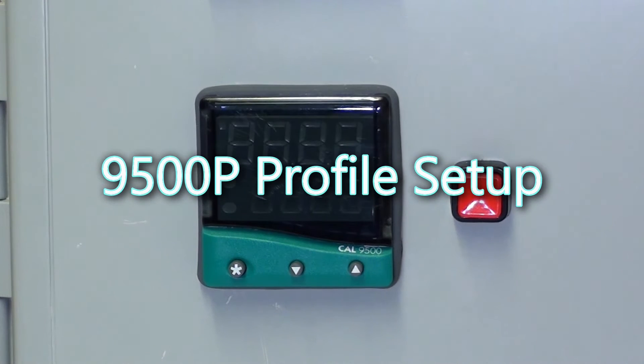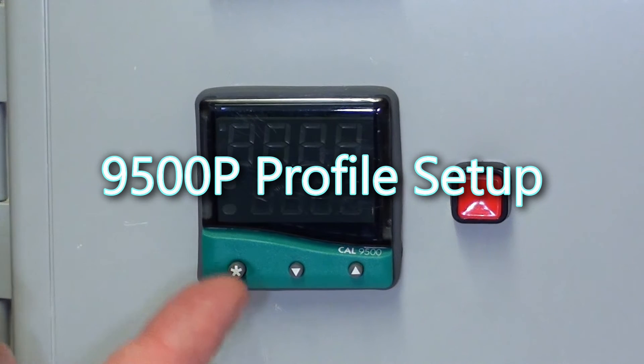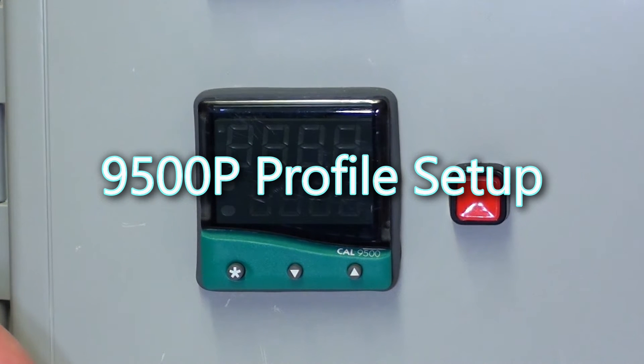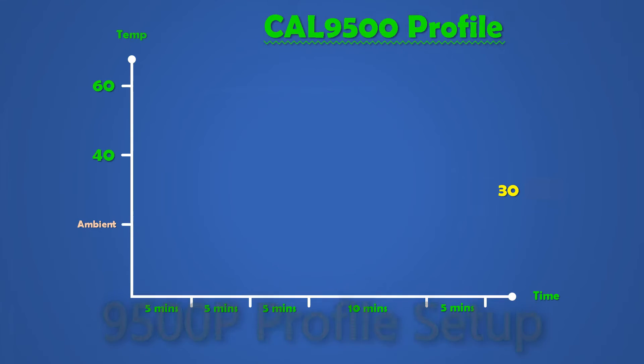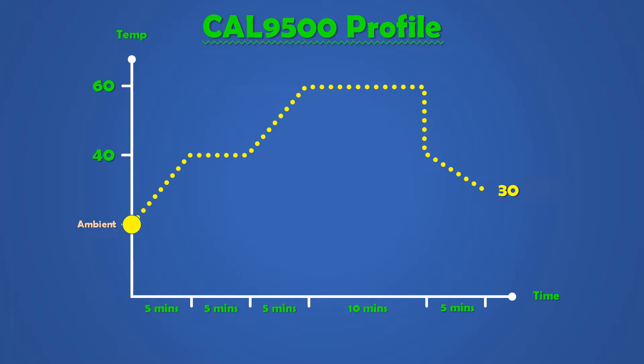This video will explain how to use the Cal 9500P as a profiler. This is the program that we want to run. We want it to ramp up to 40 degrees C, and then stay there for 5 minutes. And then ramp up to 60 degrees C, stay there for 10 minutes, and then drop down to 40, and then ramp down to 30. And we want that on a loop.